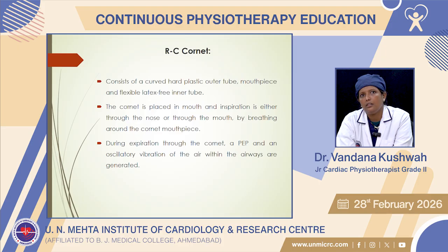The RC Cornet consists of a curved hard plastic outer tube, a mouthpiece and a flexible latex-free inner tube. The Cornet is placed in the mouth, and inspiration is either through the nose or through the mouth.